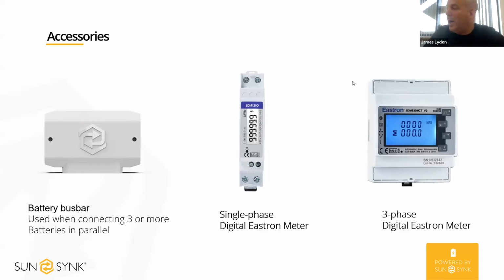We do stock Eastron meters as well. So if you've got a job where the CT is quite far away from the inverter, the standard CTs that ship with the inverter can be extended up to about 15 meters. Anything longer than that, we always recommend using the Eastron meter. That's going to give us a clear signal. It's going to get rid of any potential noise. So yeah, we do stock them.